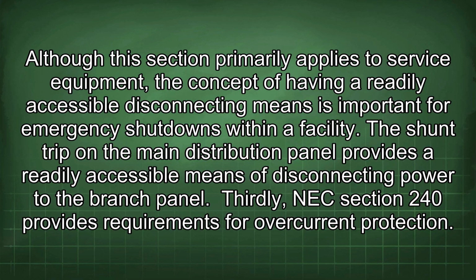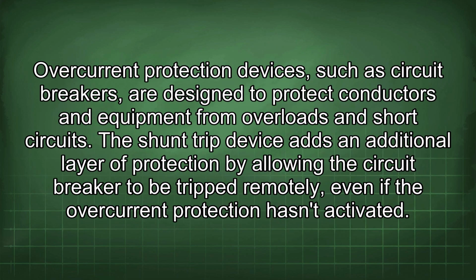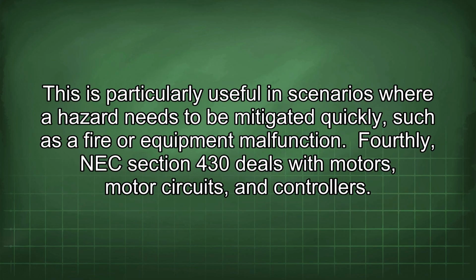Thirdly, NEC Section 240 provides requirements for overcurrent protection. Overcurrent protection devices, such as circuit breakers, are designed to protect conductors and equipment from overloads and short circuits. The shunt trip device adds an additional layer of protection by allowing the circuit breaker to be tripped remotely, even if the overcurrent protection hasn't activated. This is particularly useful in scenarios where a hazard needs to be mitigated quickly, such as a fire or equipment malfunction.